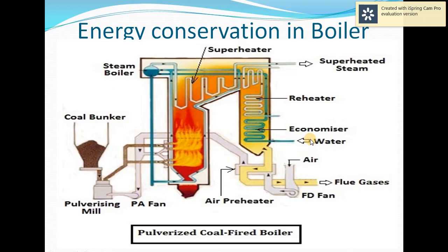Third is the water cycle. There is a feed water pump, through which water is supplied via a pipeline through the economizer heat exchanger. In the economizer, the water gets heated and flows to the drum. The water remains in a liquid state up to the drum — steam is not produced here, only heating occurs. From the drum, a downcomer carries water by gravity into the down header.